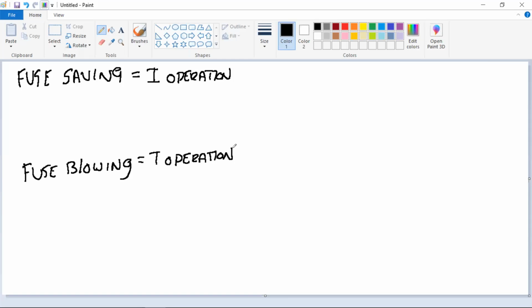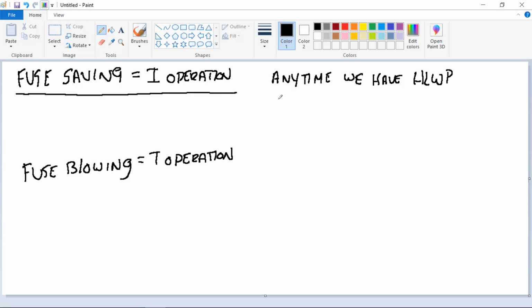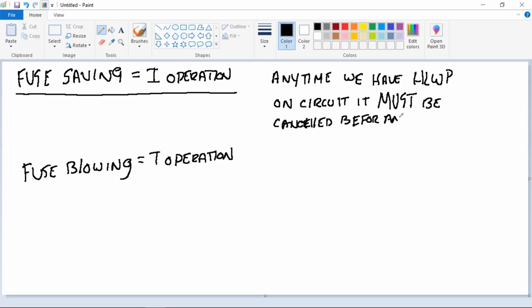All right. There's a procedure you need to follow here, especially in the fuse saving situation. And I'll use that capacitor bank that we had yesterday as an explanation. Anytime we have a hotline work permit (HLWP) on a circuit, it must be canceled before any switch close.